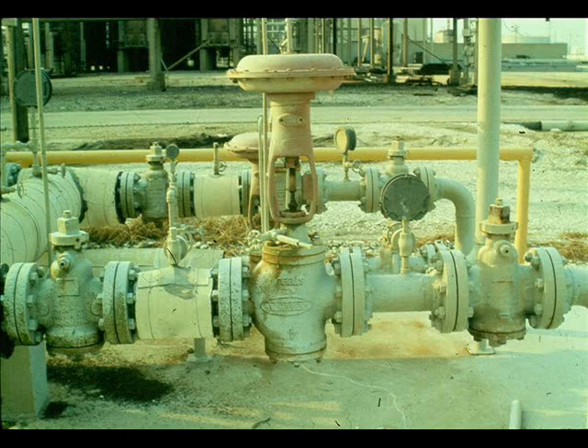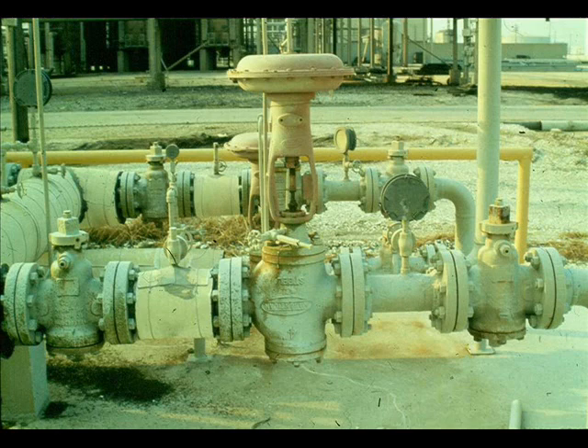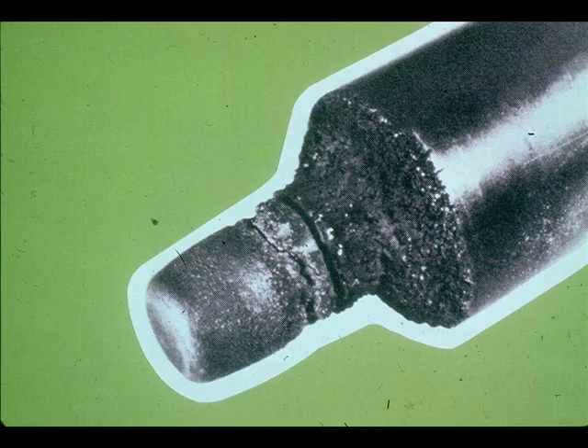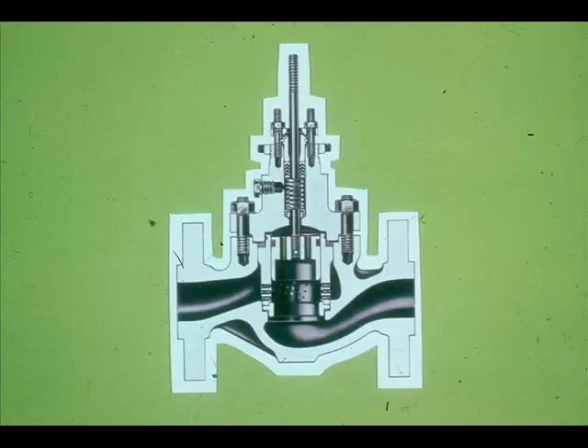A cavitating control valve sounds like it has gravel flowing through it. Cavitation is likely to occur in applications where a high pressure drop across the control valve is present. Cavitation can severely damage control valve trim.